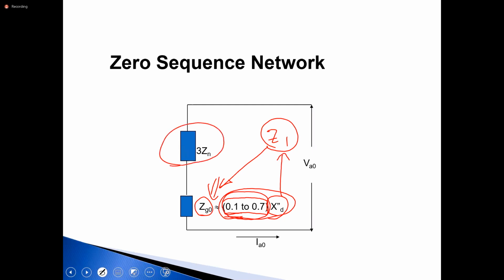Zn has nothing to do with the manufacturer, because you, as the engineer, would have installed the generator and earthed it through an impedance. So whatever the impedance that you insert in the neutral, you are going to multiply it by 3 and add it to Zg0 in order to get Z0 for your generator.